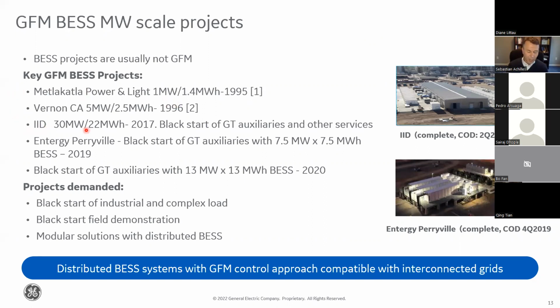It was used to black start a gas turbine. Black starting a gas turbine is really like black starting an industrial plant. You basically have to energize all the auxiliary services, motors, drives, that are required to start a gas turbine. So that's what we did in 2017.